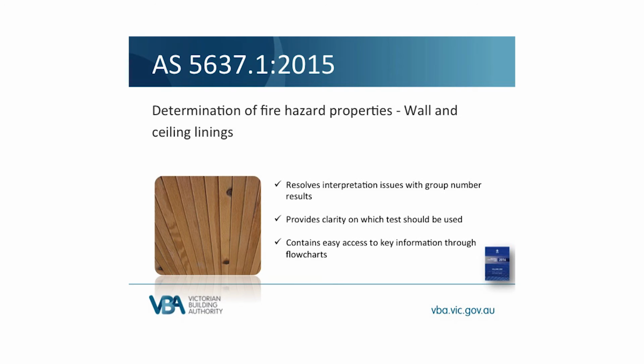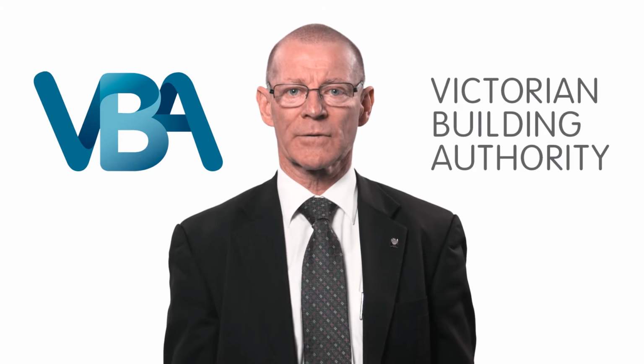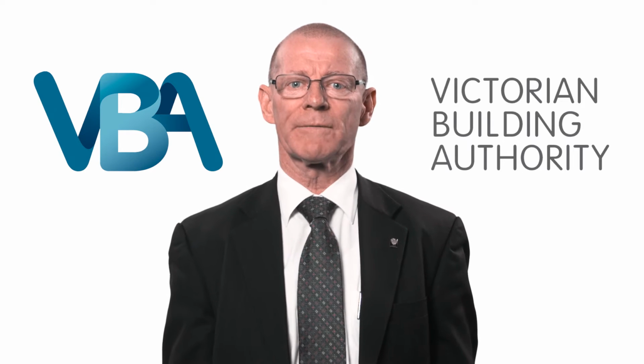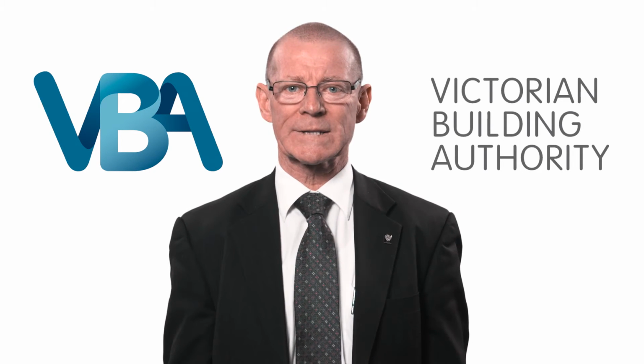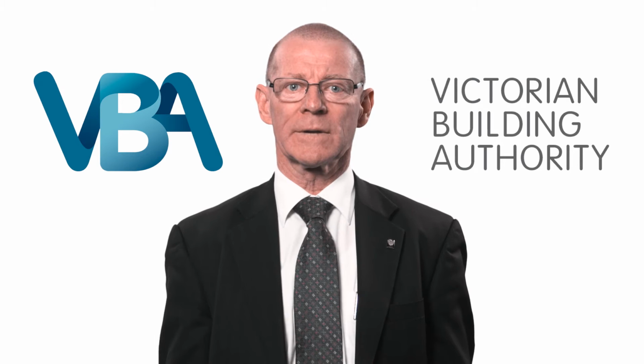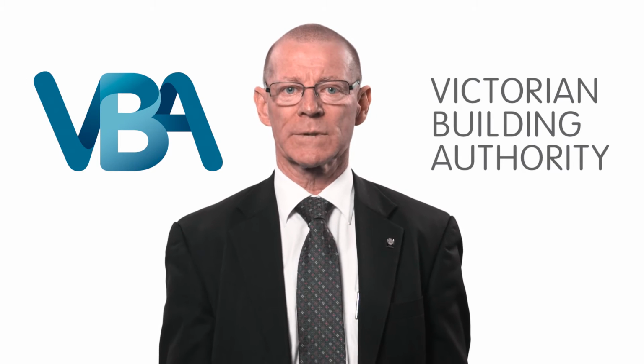This is a brand new standard that is being referenced in the NCC for the very first time. AS 5637-2015 addresses the application of the room corner test, AS/ISO 9705, and the cone calorimeter, AS/NZ 3837, to determine the fire hazard properties for wall and ceiling linings as defined in the NCC, C1.10.